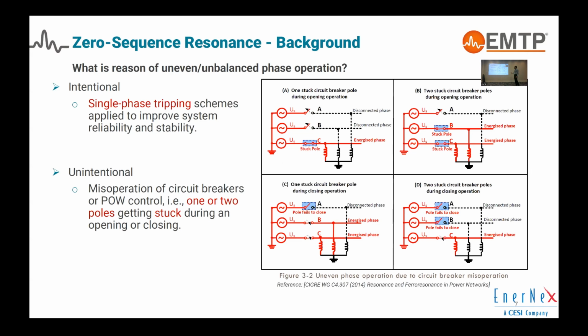For example, during the opening operation of the breaker, if one of the poles remains stuck, this is an unbalanced operation. Similarly, if two poles remain stuck during opening of the breaker, it's an unbalanced operation. Likewise, during the closing operation of the breaker, if one pole remains stuck or fails to close, we will have unbalance. And similarly, if two phases are stuck, then we will have another situation of unbalanced operation. As you can see, there are different ways in which unbalanced operation can happen. So when we run the simulation on a circuit, there would be a number of cases to run, even for a single breaker.